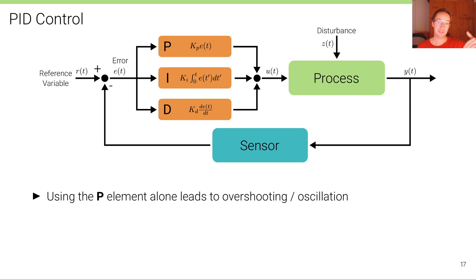Using the proportional element alone leads to overshooting and oscillation because as we are reducing the error, as soon as we pass the zero-error level, we're going into the other direction. The controller has no idea that we have already approached zero, so it continues and increases the error with a negative sign.